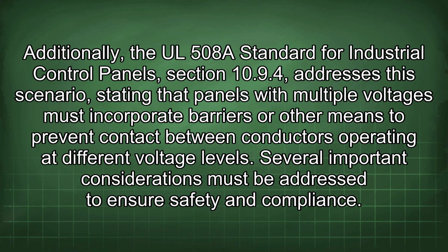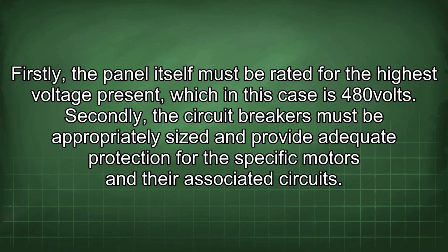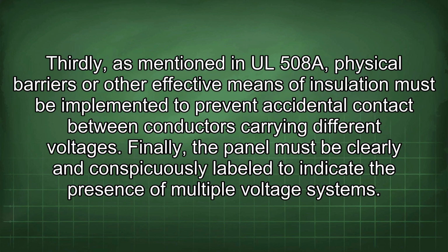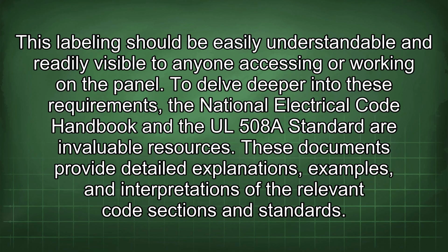Several important considerations must be addressed to ensure safety and compliance. Firstly, the panel itself must be rated for the highest voltage present, which in this case is 480 volts. Secondly, the circuit breakers must be appropriately sized and provide adequate protection for the specific motors and their associated circuits. Thirdly, as mentioned in UL 508a, physical barriers or other effective means of insulation must be implemented to prevent accidental contact between conductors carrying different voltages. Finally, the panel must be clearly and conspicuously labeled to indicate the presence of multiple voltage systems. This labeling should be easily understandable and readily visible to anyone accessing or working on the panel.